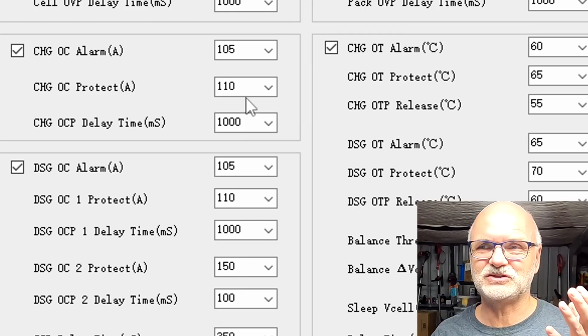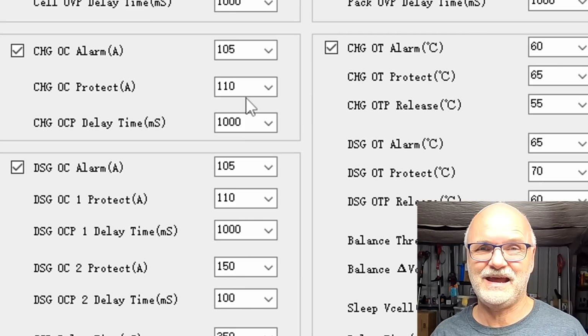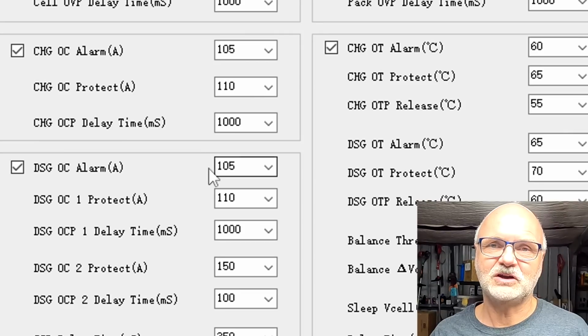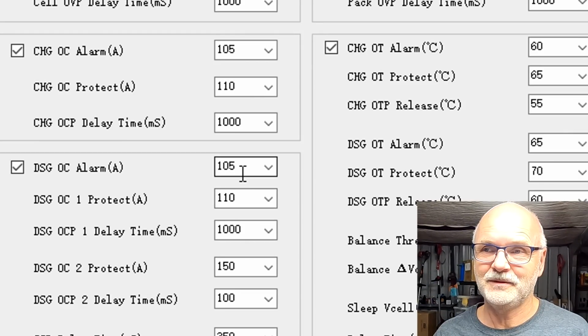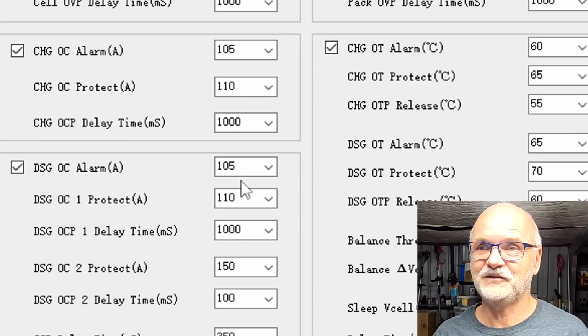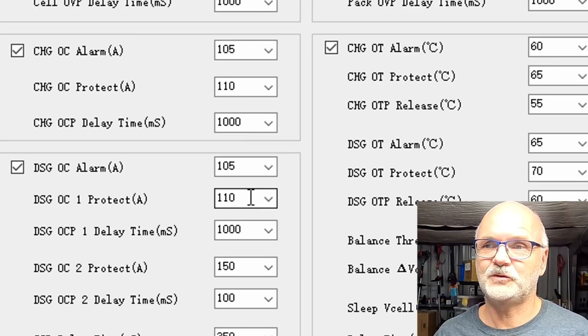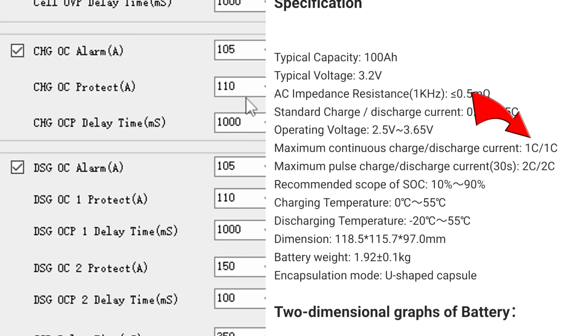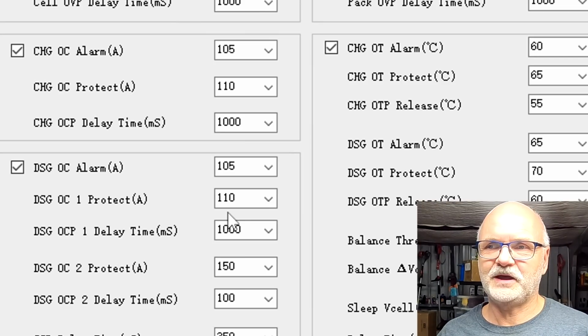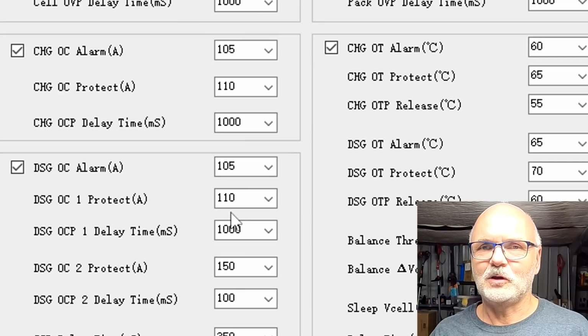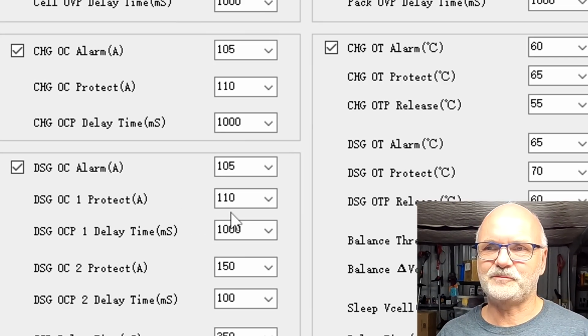I mean, who is charging such a small battery with 100 amps? That is crazy. Discharge is exactly the same. 105 amps discharging alarm, which I would like to see at 90. Discharge overcurrent protection kicks in at 110. That is 1C for these small cells. And here, discharge overcurrent protection at 150 amps. Seems to be okay as well. It covers you for spikes.